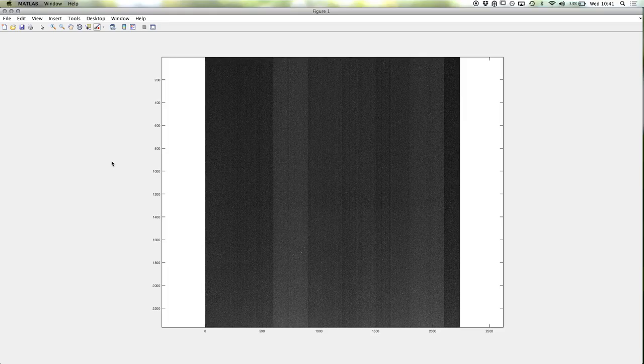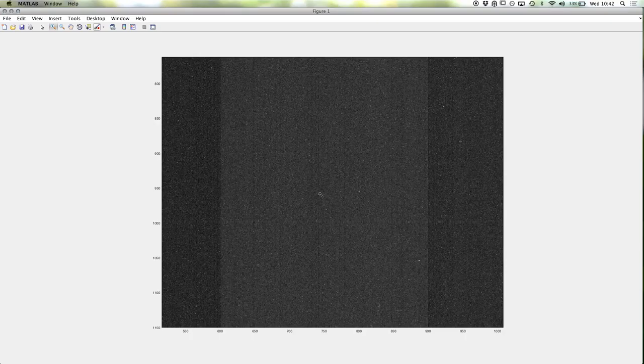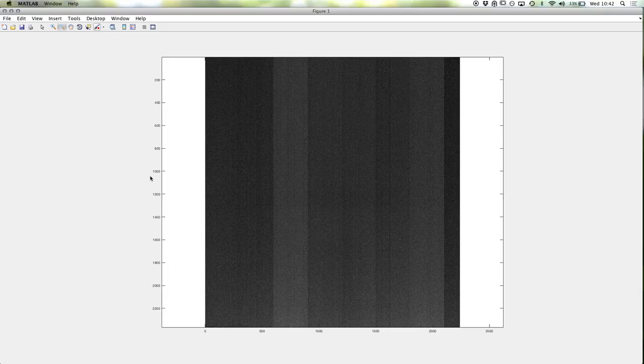No x-rays — the camera is inside a metal container, there is no information, no photons coming to the detector. So this is the electronic noise background image. It also tells that the pixels are not identical like in the mathematical ideal situation where we thought all pixels measure exactly the same thing. Here we see that when there are no photons coming in, every pixel should report zero photons, but as you see all pixels seem to be reporting a different number, and we have these weird stripes. The stripes appear because of the internal structure of the detector — it consists of slabs of semiconductor material that Hamamatsu used to build this detector.